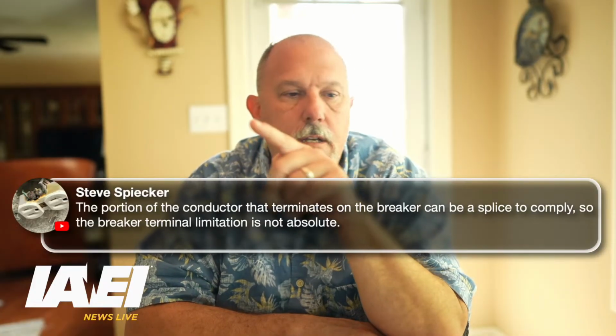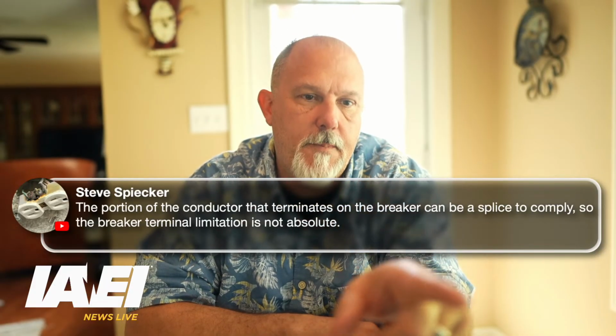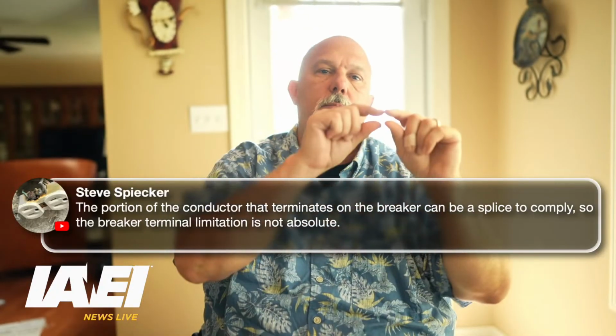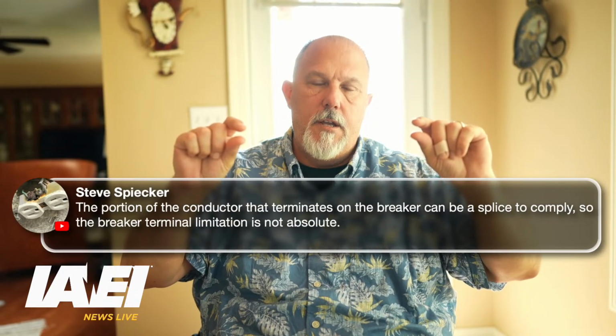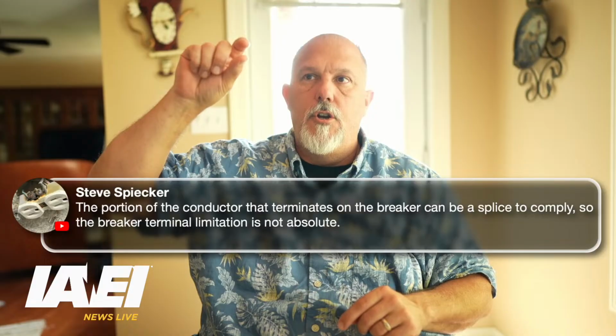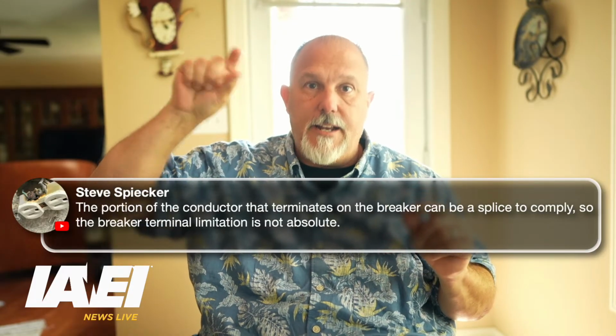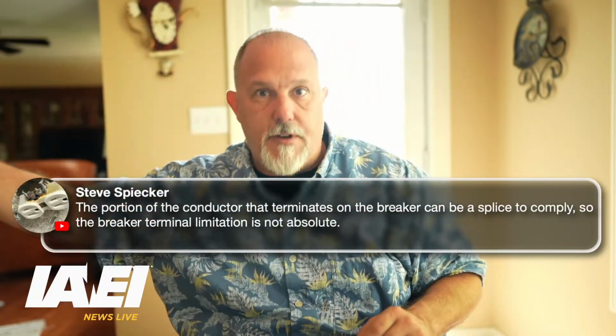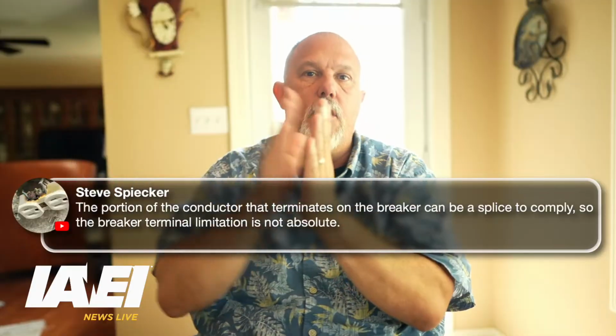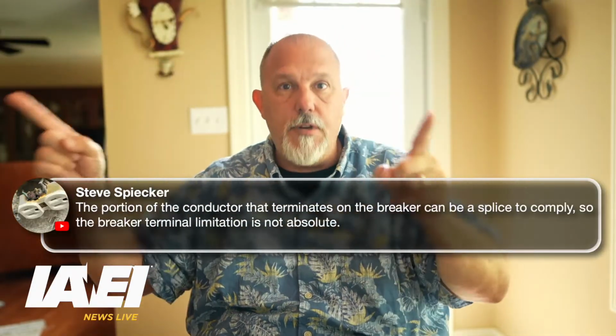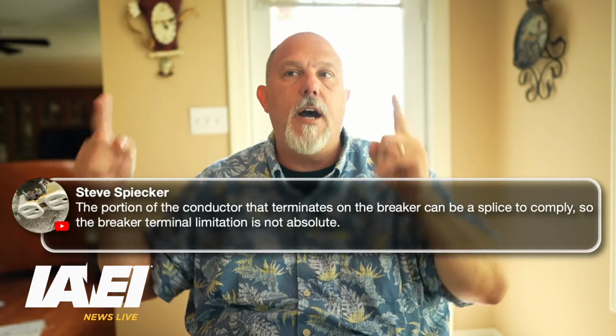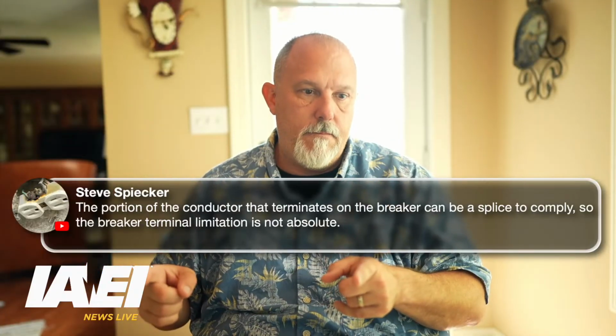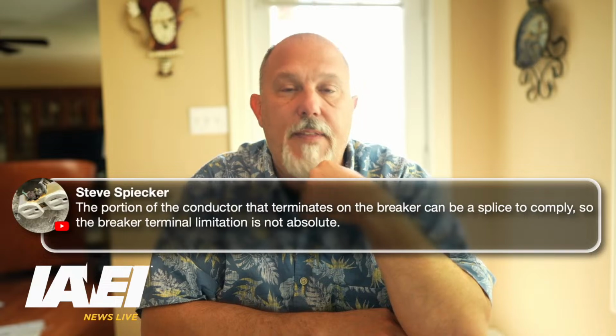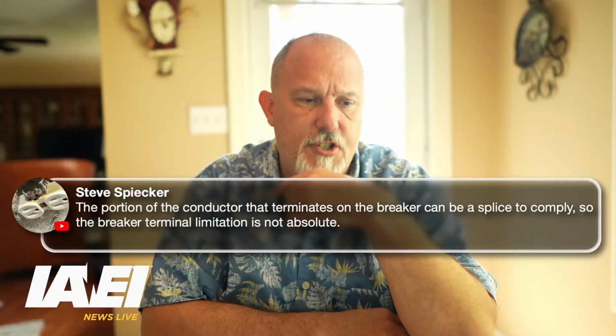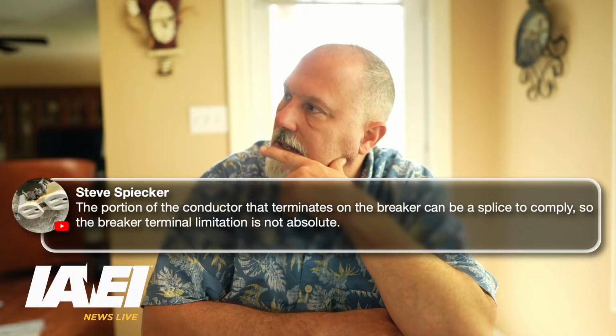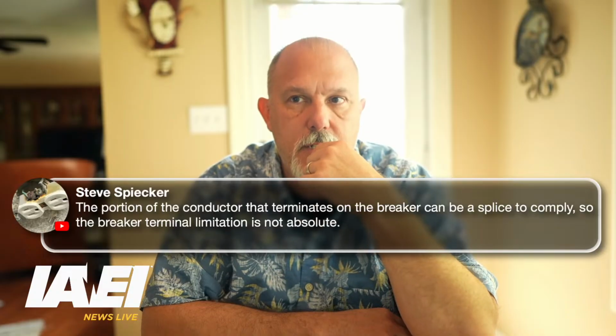I think what you're saying, Steve, and correct me if I'm wrong, is that you can come off of the breaker and then land, say, on a 90 C lug in 90 C equipment and go from 90 C to another 90 C. So that portion of the conductor on the other side of that splice that's in between two 90 C pieces of equipment, I can have at a different temperature rating. And I would agree with that. I'm not sure what you mean. I think that's what you mean. The portion of the conductor that terminates on the breaker can be a splice. I'm not sure what that means.